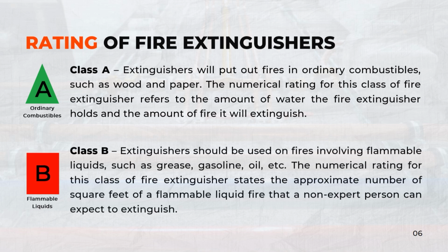Class B extinguishers should be used on fires involving flammable liquids, such as grease, gasoline, oil, etc. The numerical rating for this class of fire extinguisher states the approximate number of square feet of a flammable liquid fire that a non-expert person can expect to extinguish.